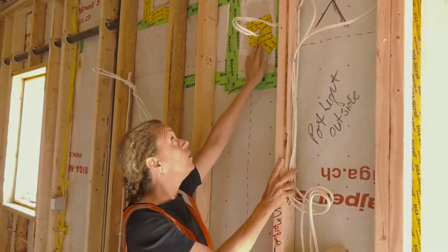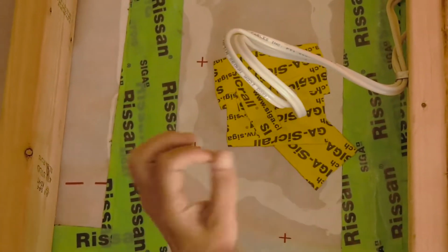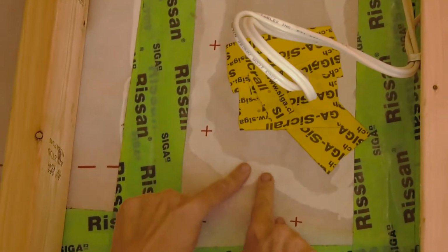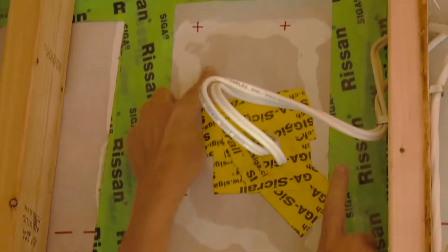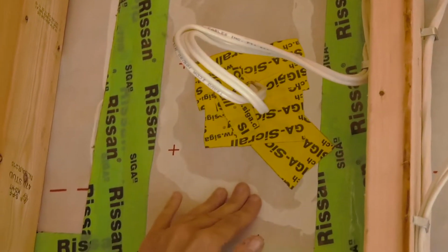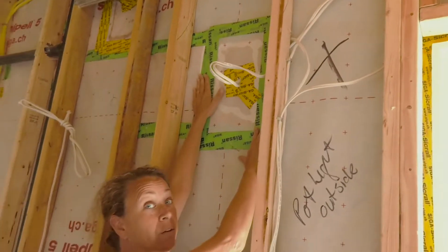What does that do? Look how they've sealed it. So it goes all the way through. They've sealed it on the outside. They've sealed it on the inside. Not only that, they've caulked around where the air barrier is on this penetration, and then they've taped around. A substantially airtight house, better than code or substantially better than code, could see 10 or 12% increases or enhancements.